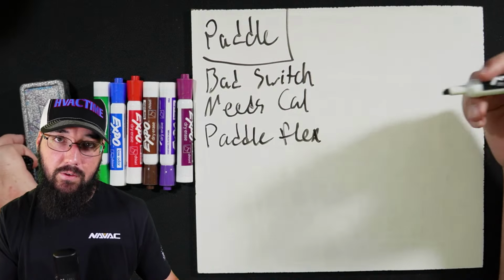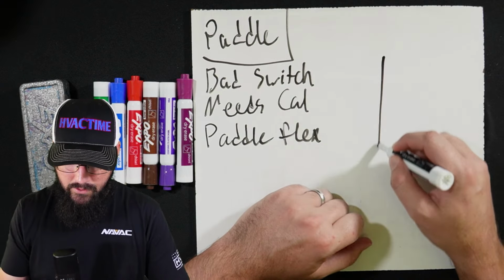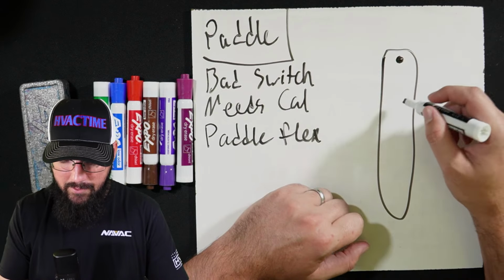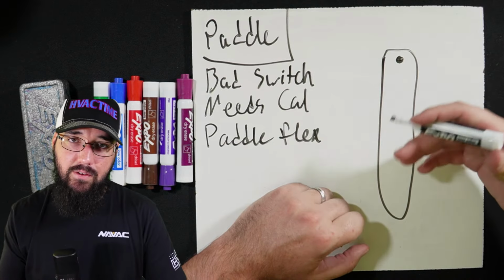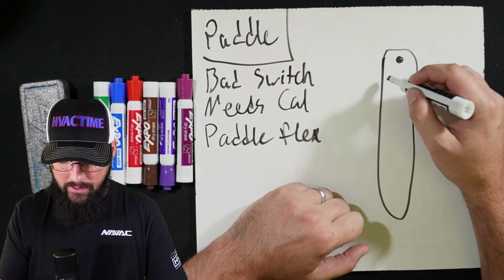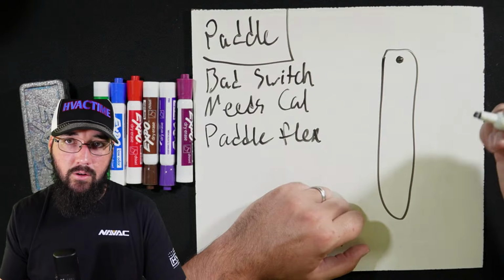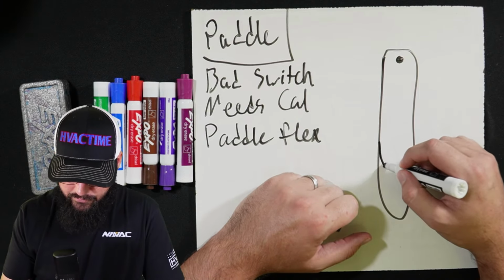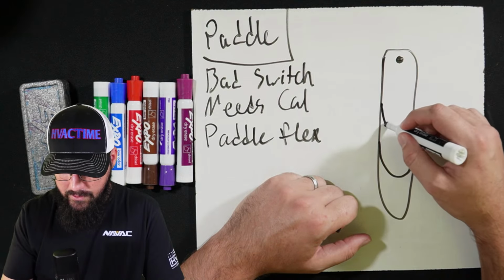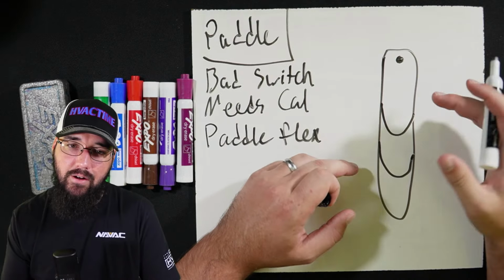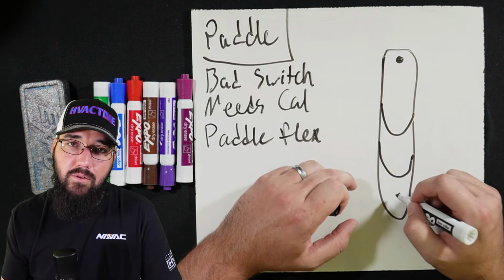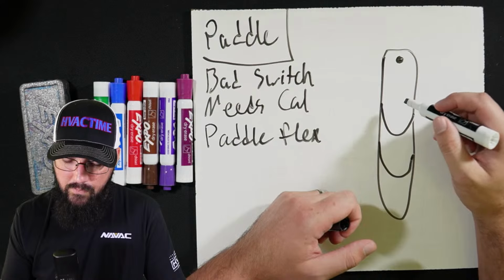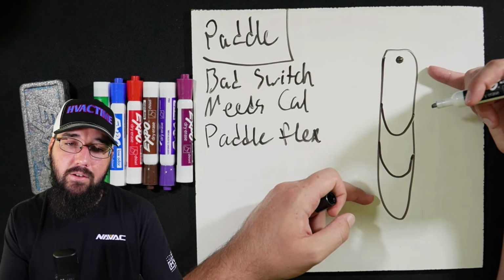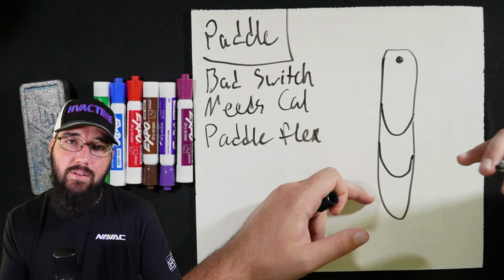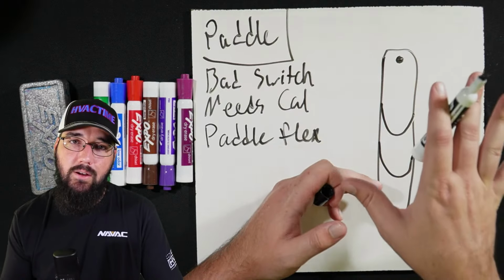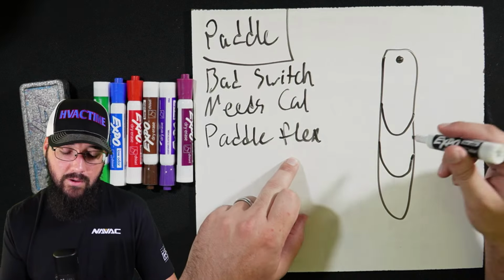When I say paddle flex, these paddle switches come with multiple of the little paddles in there, right? So what you want to do in that scenario is, on the back side facing away from the water flow, add those shorter paddles if you're using a longer one on a larger pipe. You could have up to 2 or 3 of the supporting paddles on the back side, giving it more rigidity. One of the issues you'll run into is these long paddles tend to have a lot of flex, and you don't want that flex. It's just the nature of a long paddle. So we have to add those others as a support to give it more rigidity so that it will trigger properly. All right, so paddle flex could be an issue. That'd be something to look into.